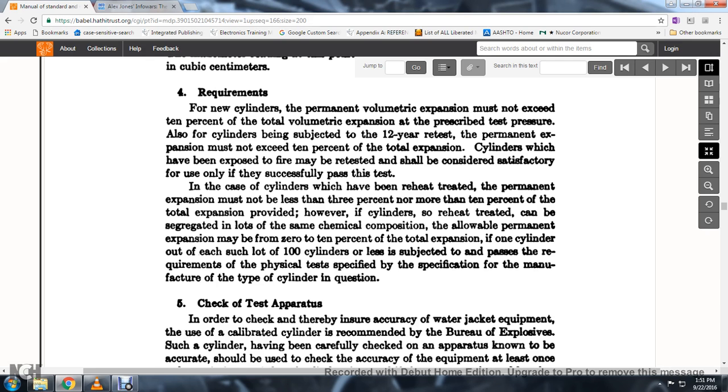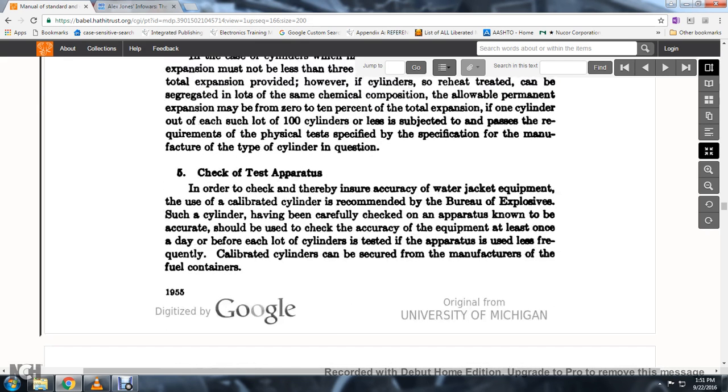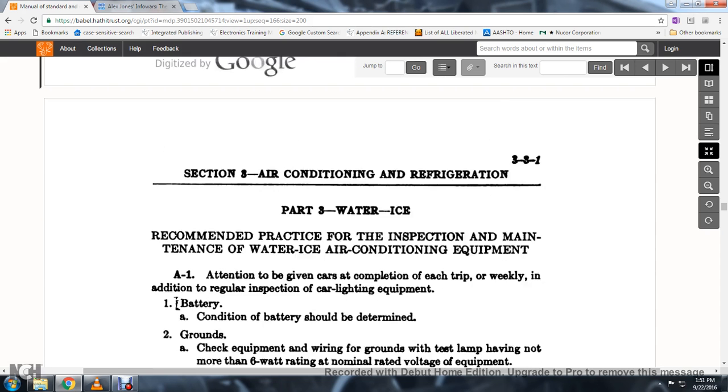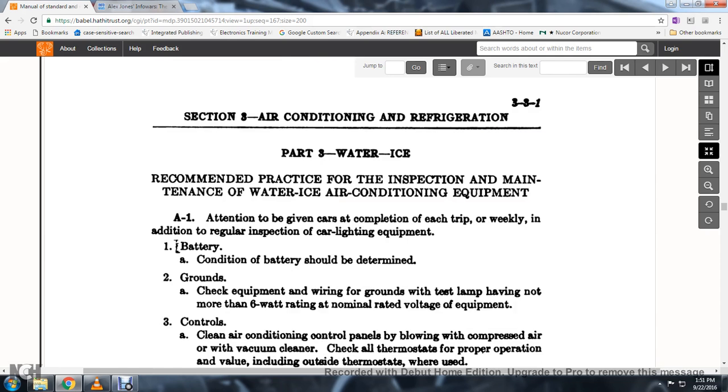In the case of cylinders that must be reheated and treated, the permanent expansion must not be less than 3 percent or more than 10 percent of the full expansion, provided the cylinder so reheated can be segregated. Permanent expansion may be from zero to 10 percent of the total expansion. To check the test apparatus accuracy, the use of calibrated cylinders of record is recommended by the Bureau of Explosives; such cylinders should be used to check the accuracy of the equipment at least once a day or before each lot of cylinders is tested.